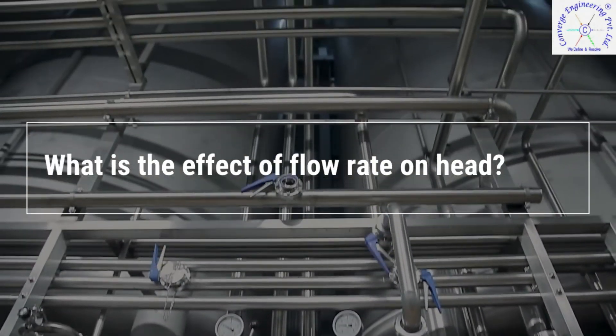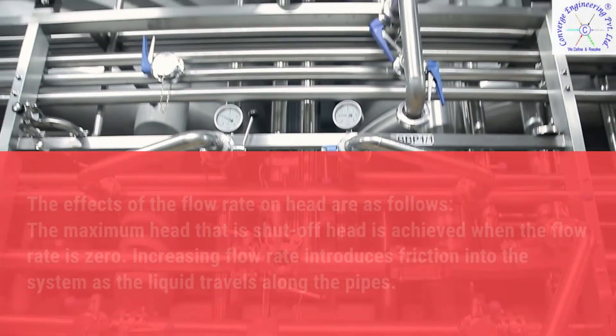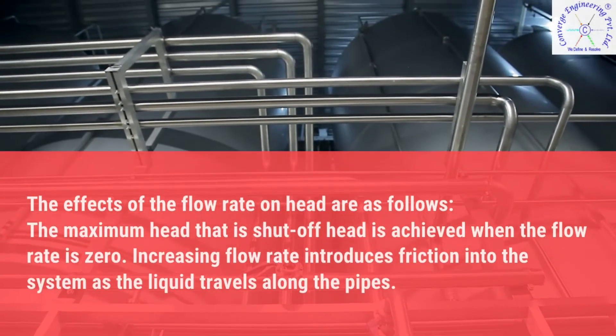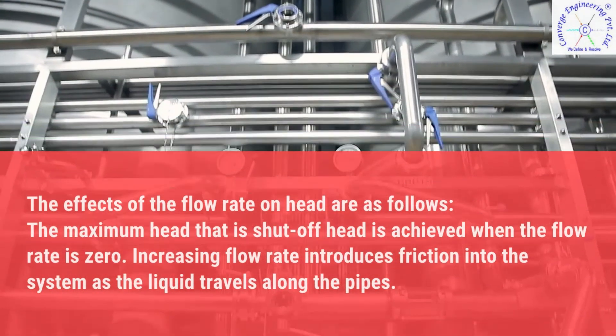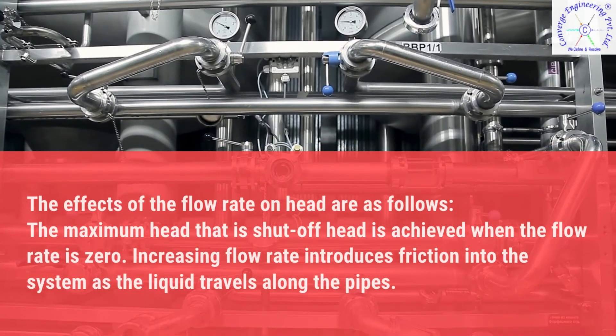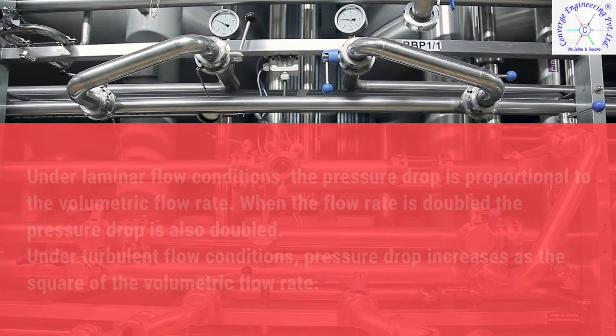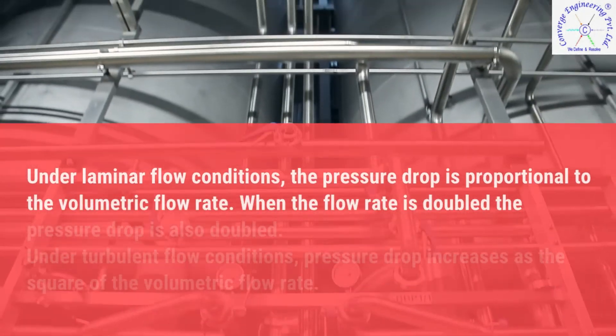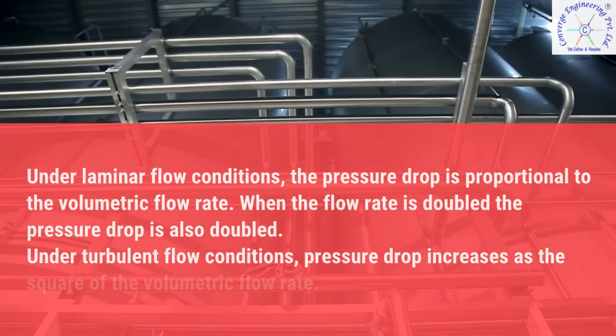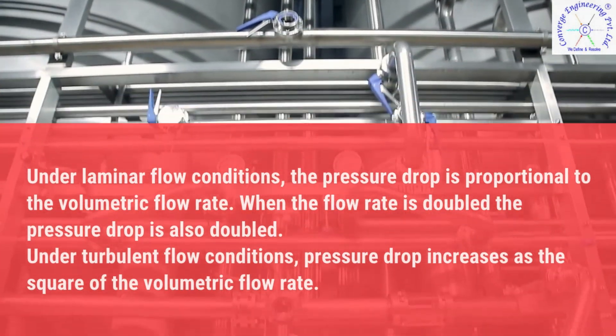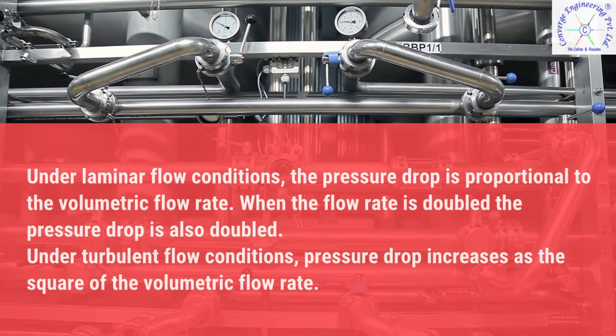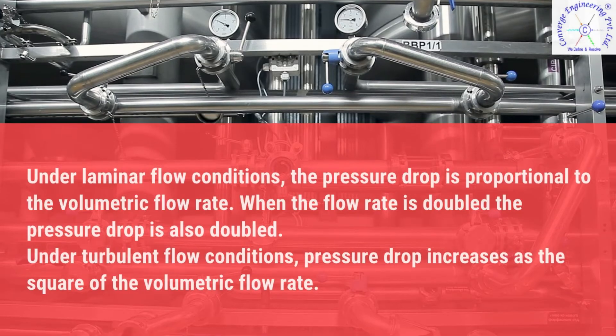What is the effect of flow rate on head? The maximum head, that is shut off head, is achieved when the flow rate is zero. Increasing flow rate introduces friction into the system as the liquid travels along the pipes. Under laminar flow conditions, the pressure drop is proportional to the volumetric flow rate; when the flow rate is doubled, the pressure drop is also doubled. Under turbulent flow conditions, pressure drop increases as the square of the volumetric flow rate.